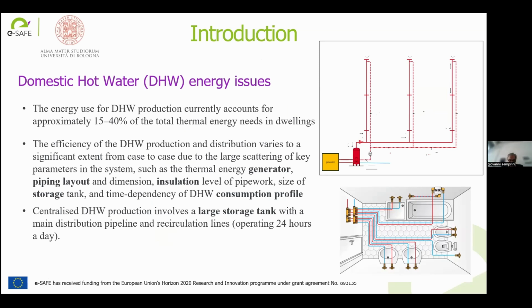Many studies in the literature report that the energy efficiency of domestic hot water systems is surprisingly low, and a significant amount of the heat is lost from the hot water before it reaches the draw-off points. This happens especially in centralized domestic hot water production, like in the picture, that involves a large storage tank, a large pipeline and a recirculation line operating 24 hours a day. The hot water at higher temperature circulates all day, producing very high thermal losses.